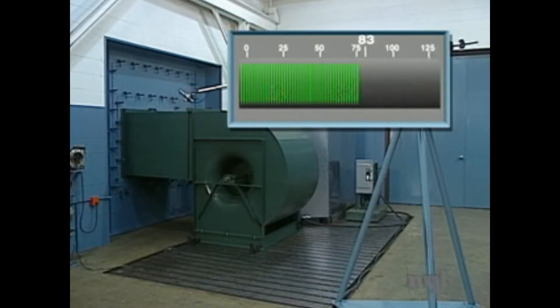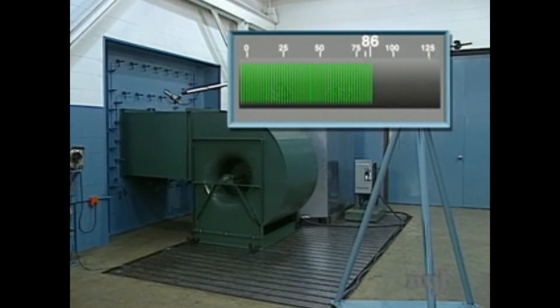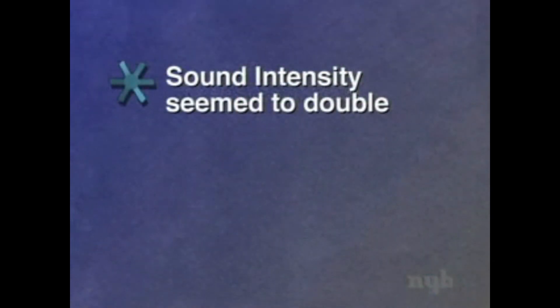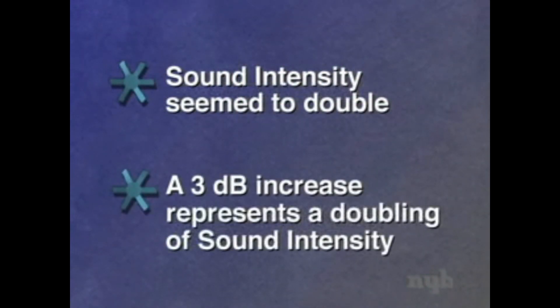Looks like our technicians are ready to run a sound test. To visualize the test better, we've provided a simulated sound pressure meter to show actual dB levels measured in the test. In this test, we will demonstrate the effect that fan speed has on sound. Initially, the fan will operate at 1200 RPM — notice that the corresponding dB level is 83. Now, if we speed the fan up to 1500 RPM, you can hear and see the difference. Notice that the sound intensity seemed to double. So remember, the decibel scale is not linear.